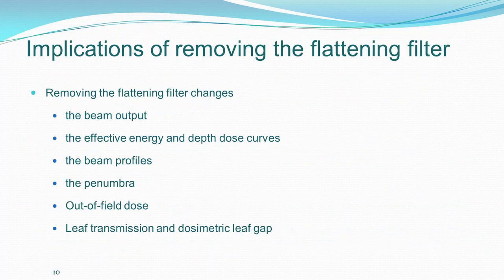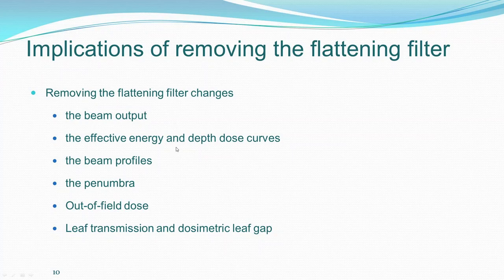What are the implications of removing the flattening filter? Removing it is not simple. Beam output increases because there is no attenuation by the flattening filter. The effective energy is decreased, so depth-dose characteristics will be different. Beam profiles undergo very different changes — the profile is not the same, the penumbra changes, and how to measure penumbra becomes a question. Out-of-field dose is advantageous. You also have to consider leaf transmission and dosimetric leaf gap.